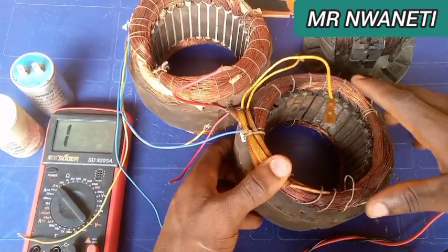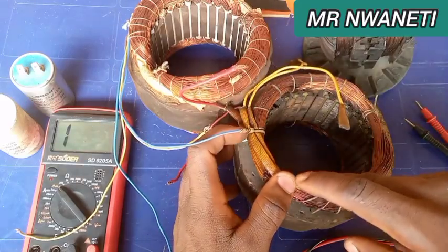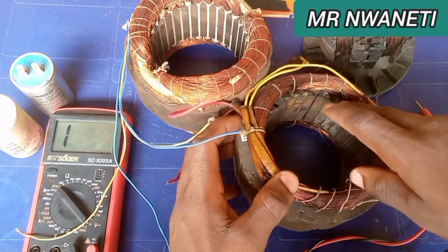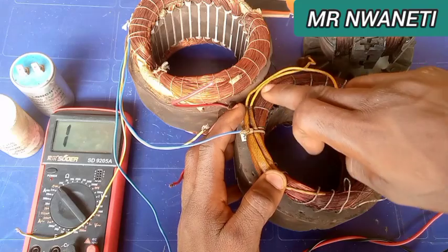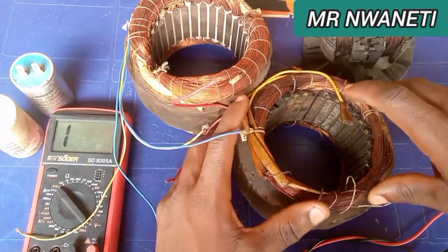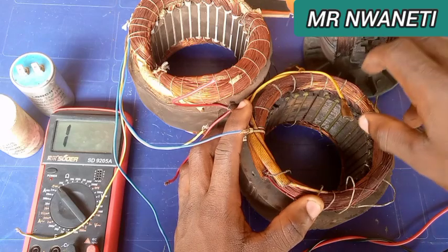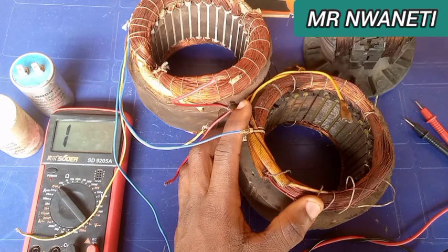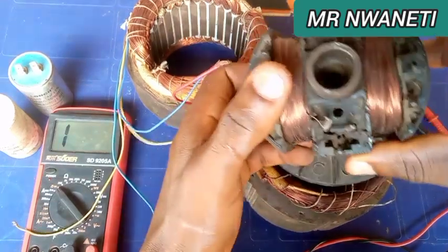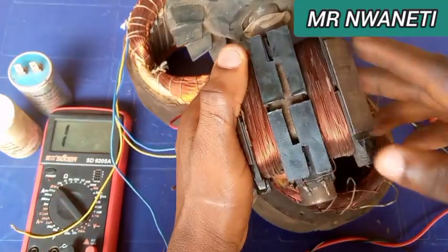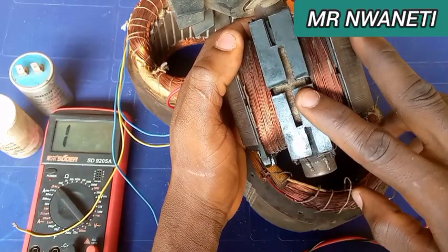So that is the main thing here. The main thing, like I already displayed before, is to increase the voltage if the speed is constant by adding more turns in the exciter, or adding more turns in the mains coil output, or by putting more turns in the rotor, I mean in the armature. Make sure, when you are putting more turns in this armature, you calculate it to avoid the smash.